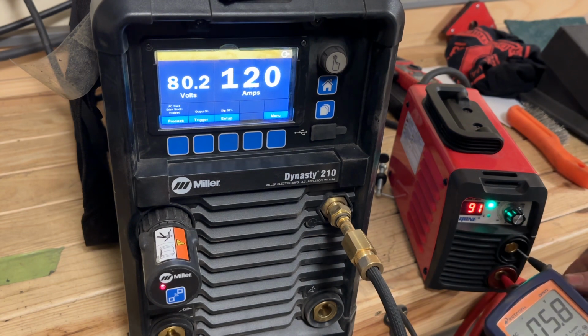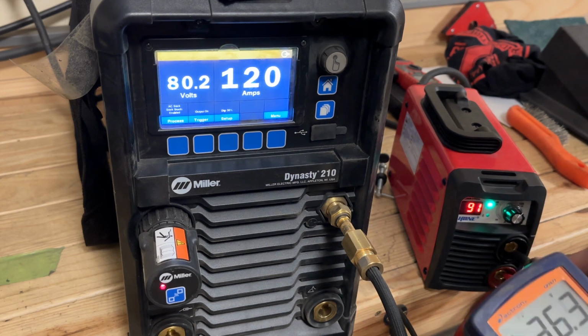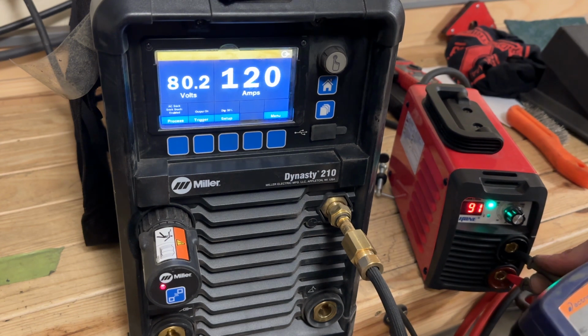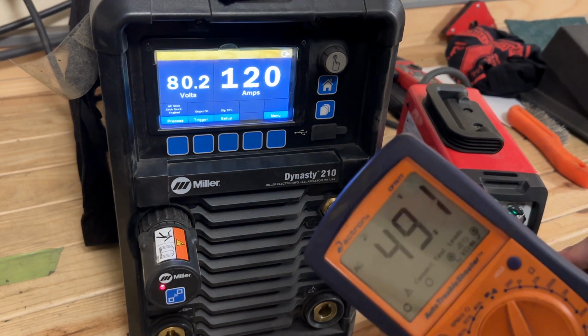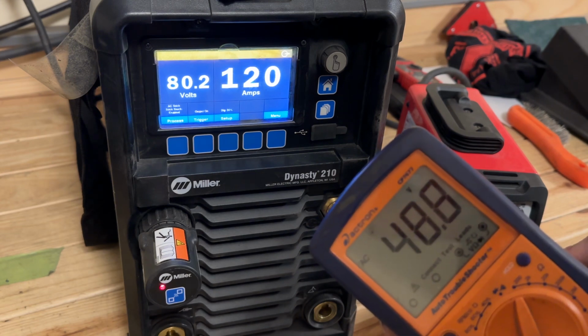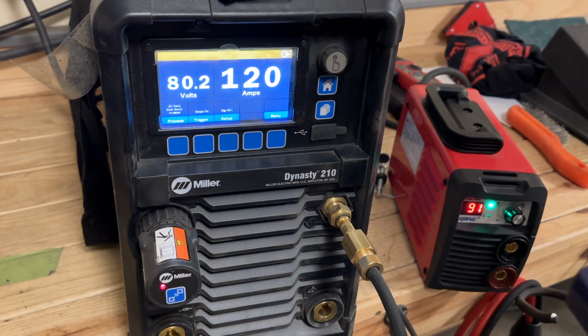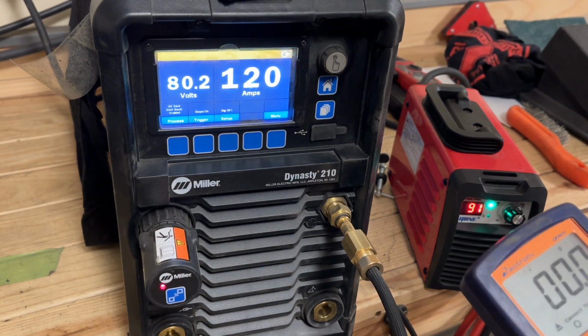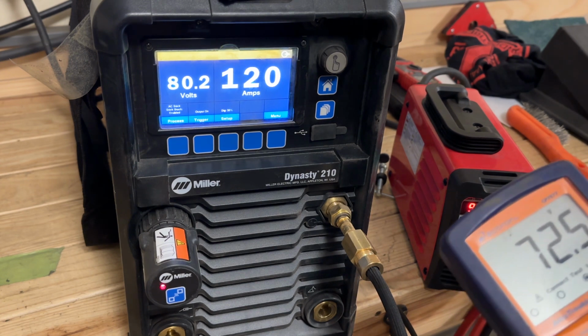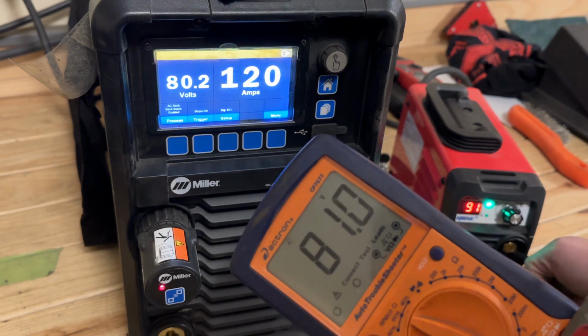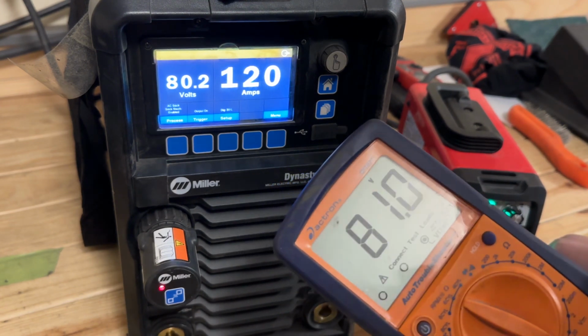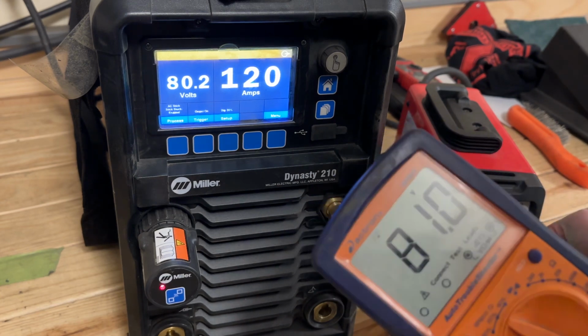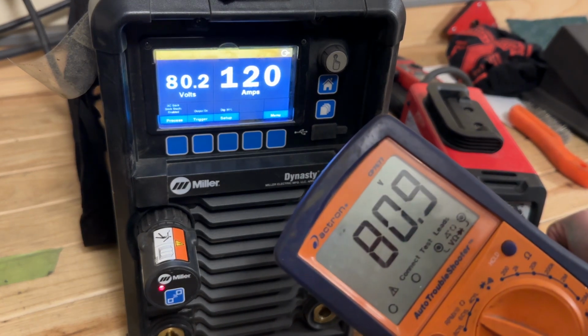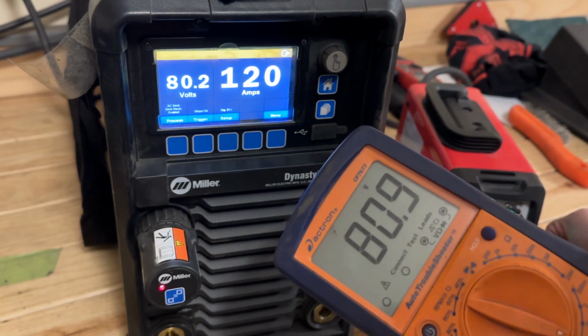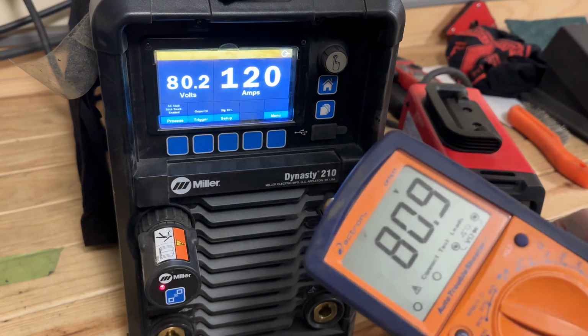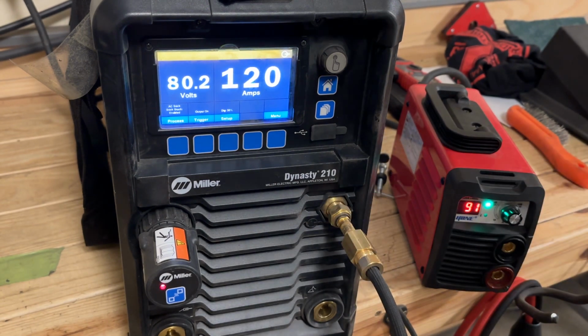Now what we're testing here is open circuit voltage, when there's no welding current. See, that's pretty interesting—I left it on AC, and it's reading output of AC current. Very interesting, since this is a DC current welder. Let's go back over to 200. So it says it's outputting 81 volts. That's pretty interesting—the output on DC is apparently so dirty that it's actually outputting AC current. Not too surprising. So the open circuit voltage between these is pretty similar.